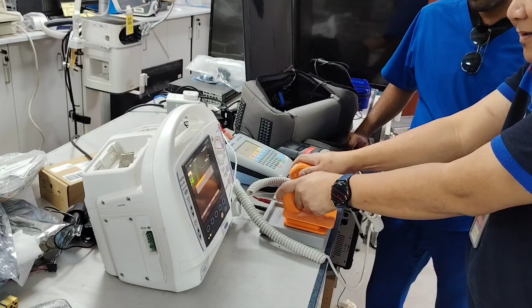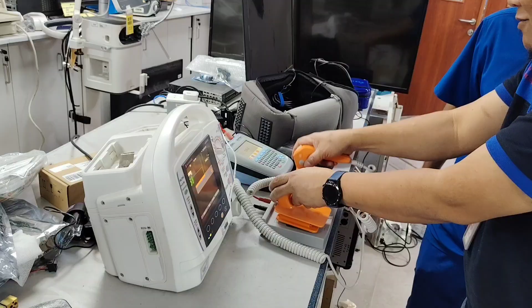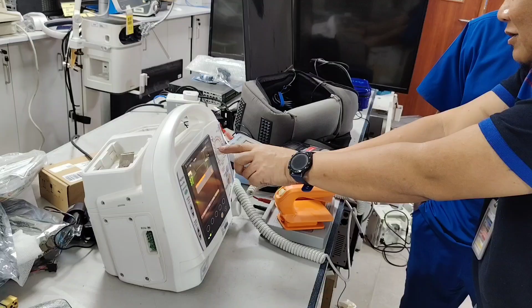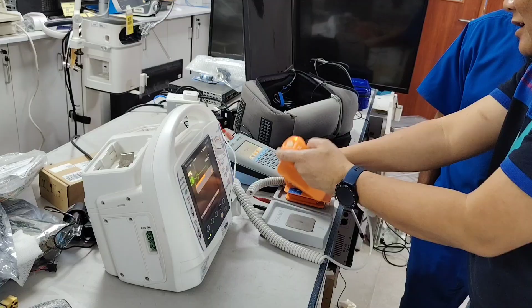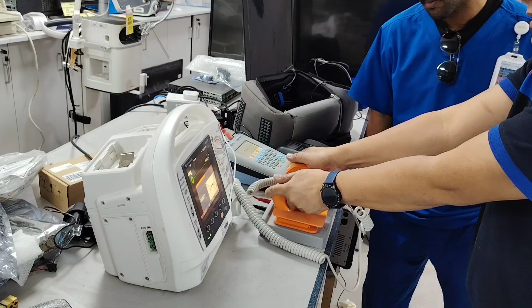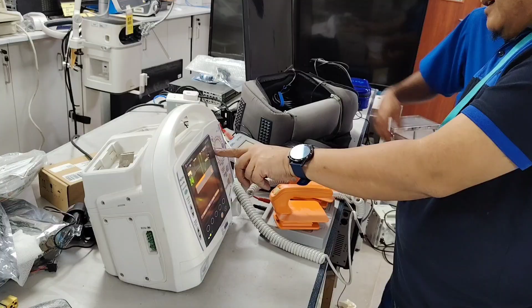You should check this one is in the paddle. Written here. Once you keep it here, you are set at 10 joules. Put this paddle, this one is sternum and this one is the apex. The apex is on the right side. Just press this button here to charge, use your thumb to charge. Then fire, discharge. So our setting is 10, and our power output is 8.5.